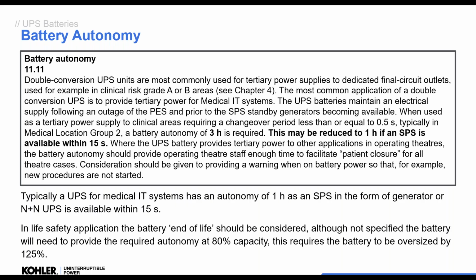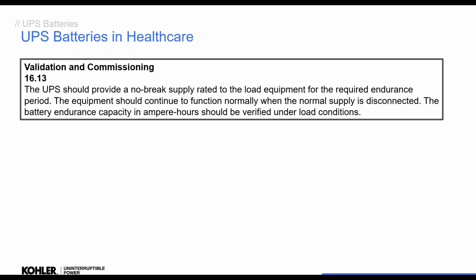One thing HTM doesn't consider is the end of life of the battery, okay? So battery will lose capacity over its life. So ideally, we should have the hour battery at end of life, okay? So that means we would have to typically oversize the battery at the beginning. The manufacturers won't put that in unless you specify that you want that, okay?